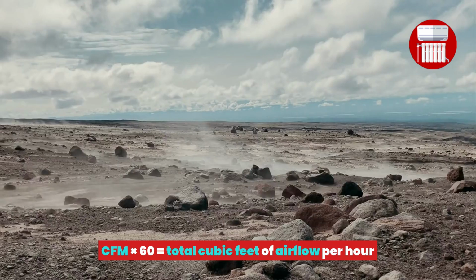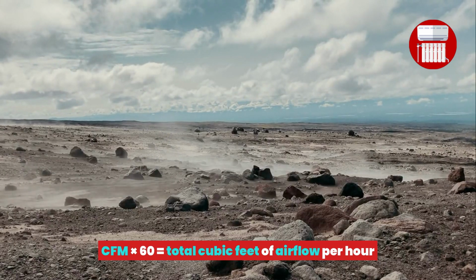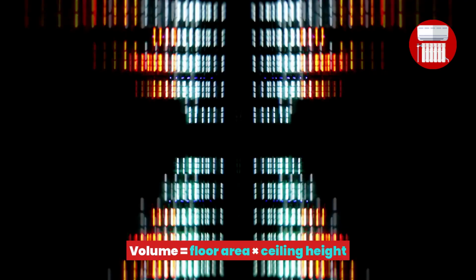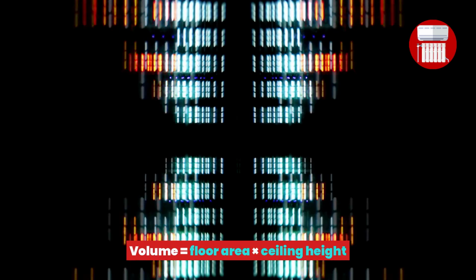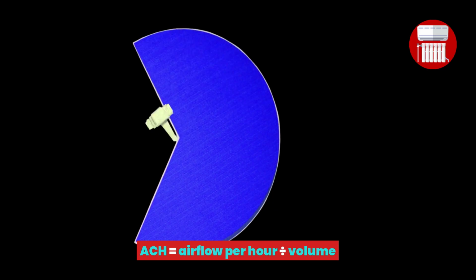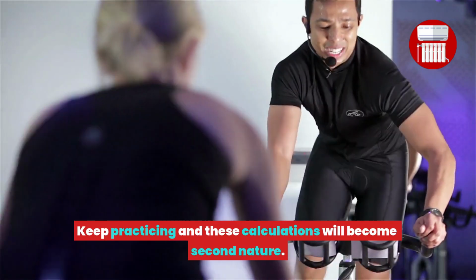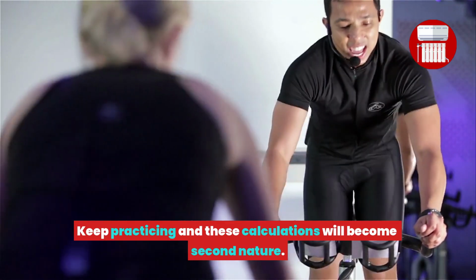Final recap. CFM x 60 equals total cubic feet of airflow per hour. Volume equals floor area x ceiling height. ACH equals airflow per hour divided by volume. Keep practicing and these calculations will become second nature.